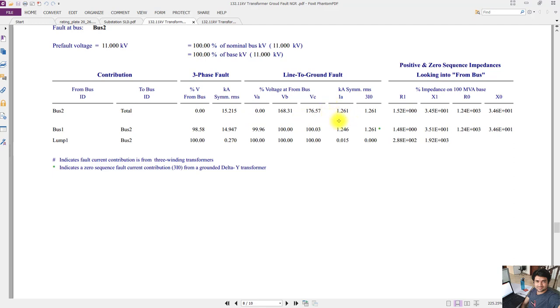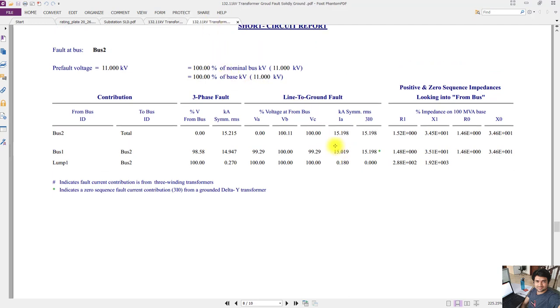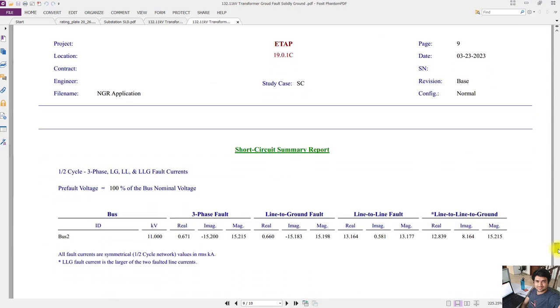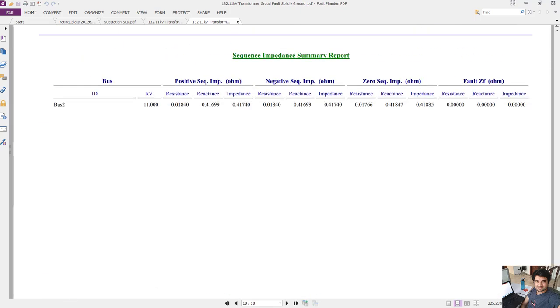Where the solidly grounded system is connected, the current value is 15.198 kilo amperes. In this you can also find out the three phase short circuit values and all possible faults are calculated here - line to line, line to ground faults.